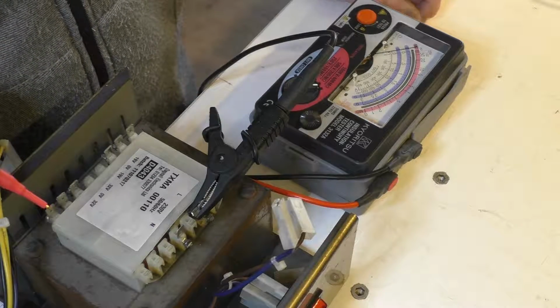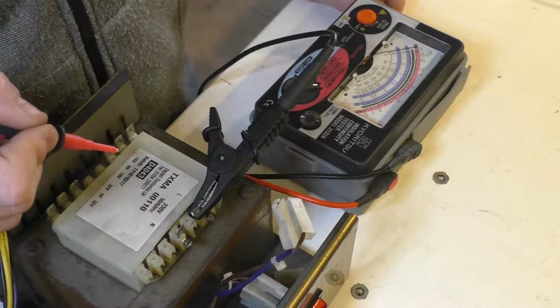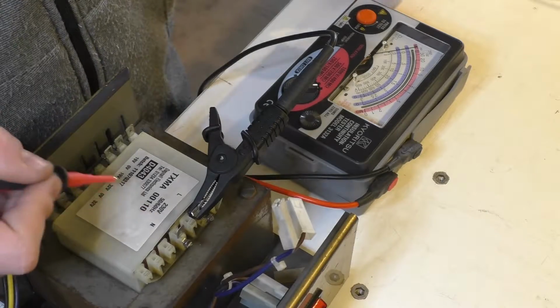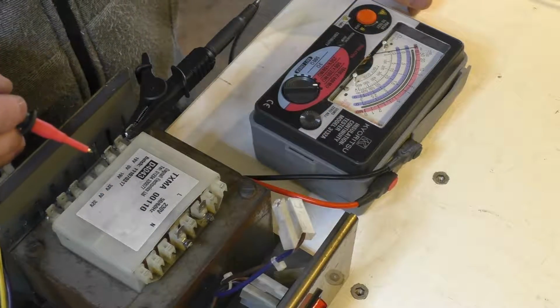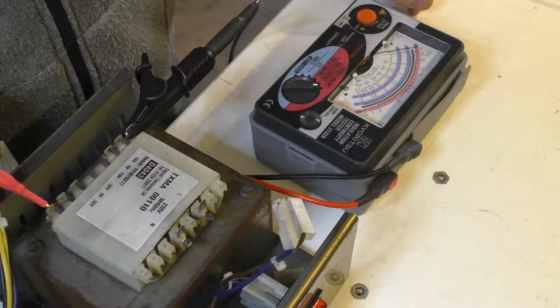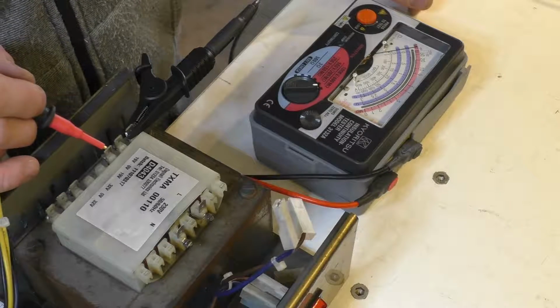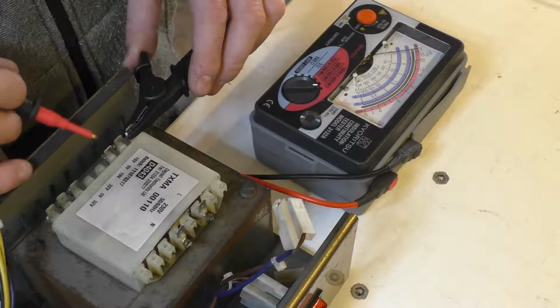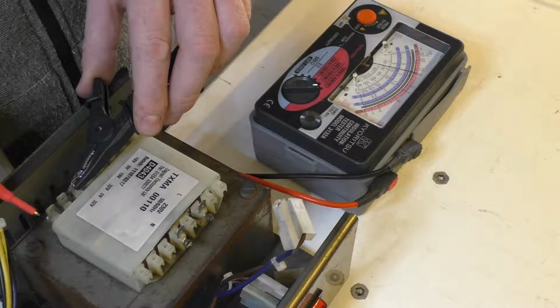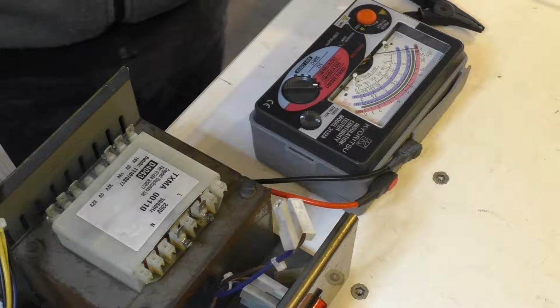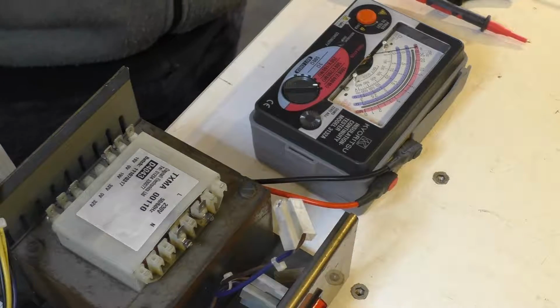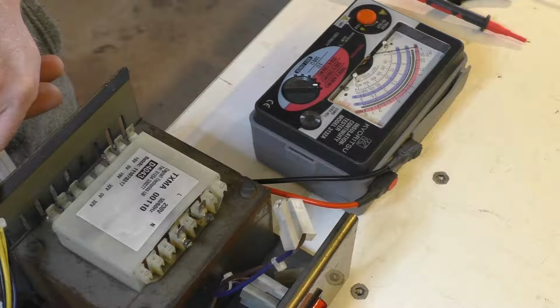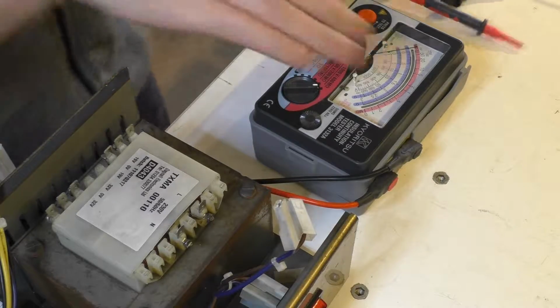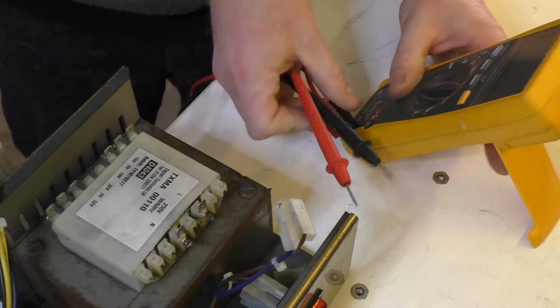Go there, showing nothing, which again is what you want. These primaries and secondaries would be pretty well isolated. There's probably a pretty heavy insulation layer between the two. These ones may not be that well insulated from each other. But, you know, that's the same one there. Yeah, don't know. Something's wrong. Could be shorted turns on the secondary. I better look up what one of these is worth if you can even get it, because that's almost like a dead short across that. You can't test it with your multimeter because it'll show a short circuit anyway because it's DC.